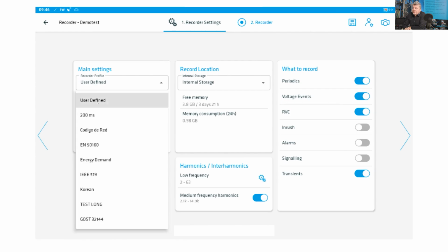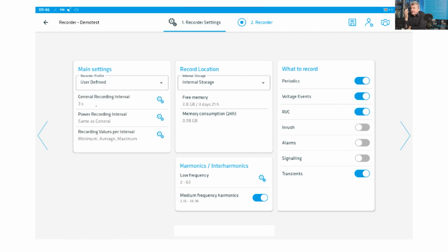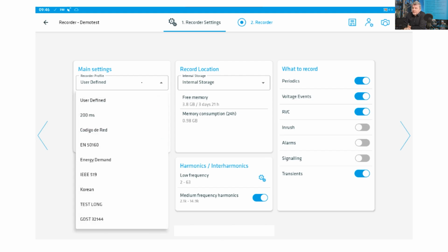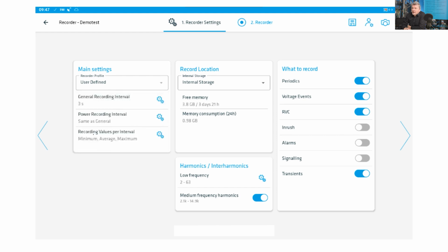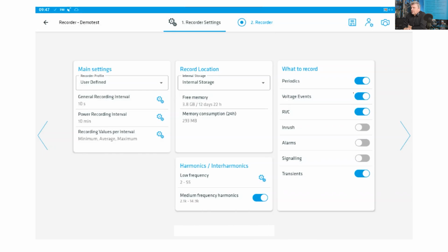As I mentioned, we have a user-defined profile, where you can select everything that is registered by yourself. Then there are predefined profiles: 200 milliseconds, Código de Red, EN 50160, energy demand IEEE, and Korean profile. We select the user-defined profile and a general recording interval of 10 seconds. For demand, 10 minutes, recording min, max, and average values. Frequencies, for example, up to 55. Also, medium supraharmonic will be measured, and we will record periodics, voltage events, and RVC.